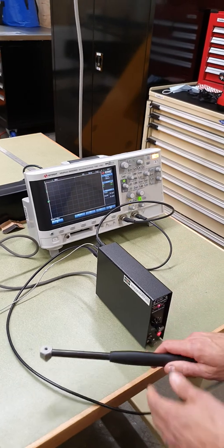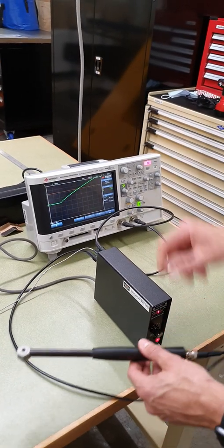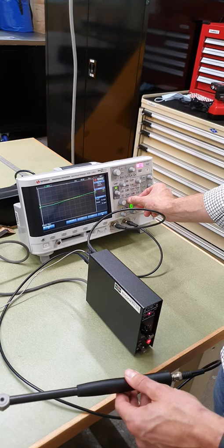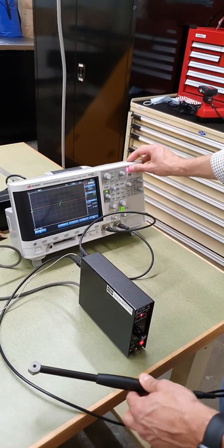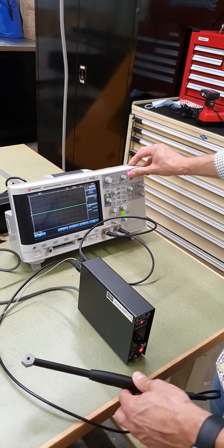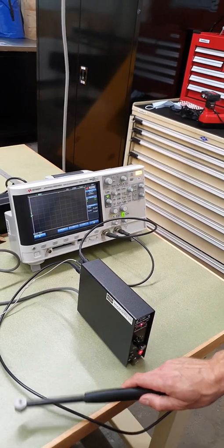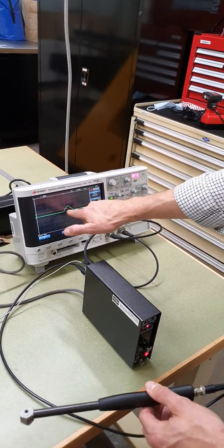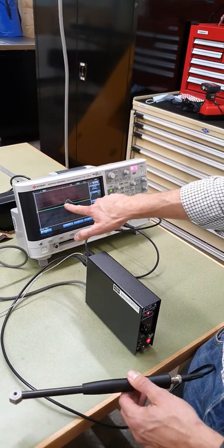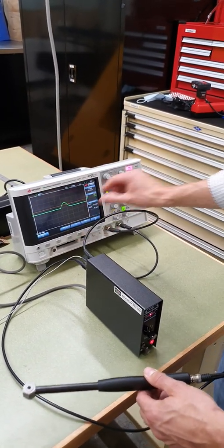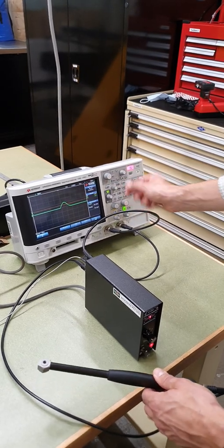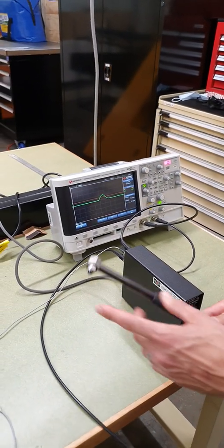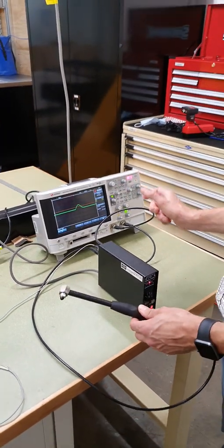When we make a measurement, you should see a much longer duration impulse. You can see I can change the time in waveform. I didn't catch all of it because the scope wasn't set up correctly. There you go. So now this time across this impulse is much longer than it was. I've changed the time base over here. I've also adjusted the force level. Heavier hammer, more force. Softer tip, longer duration.